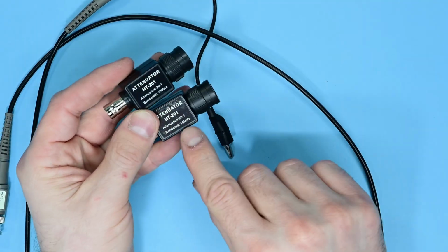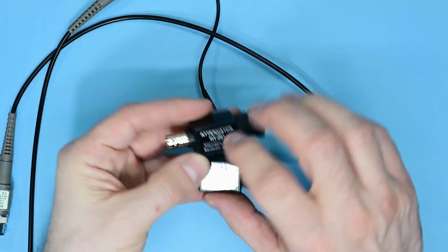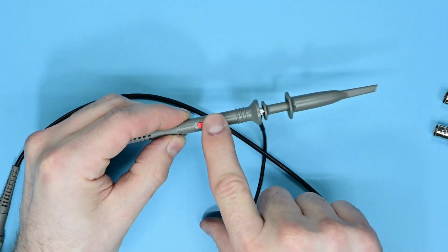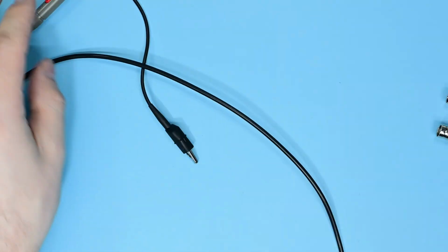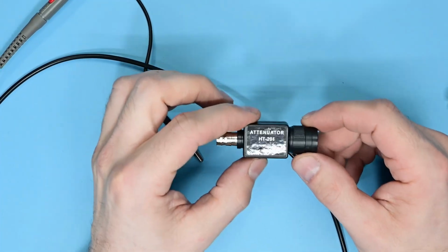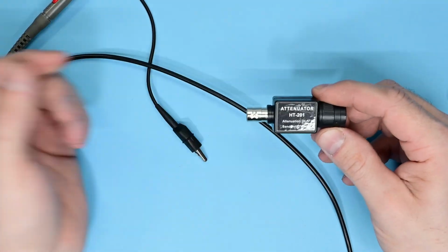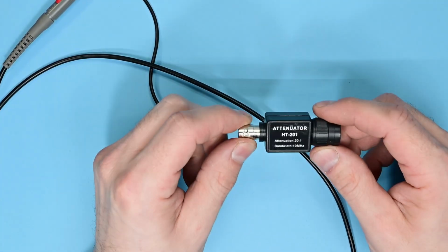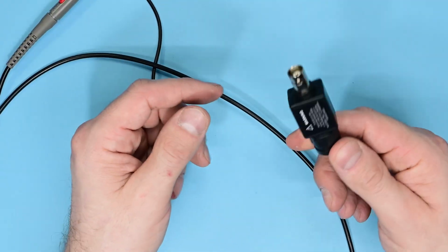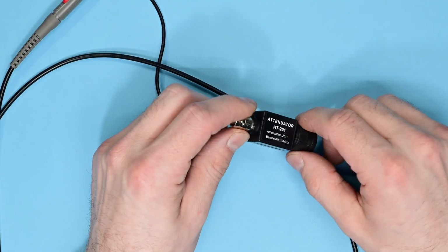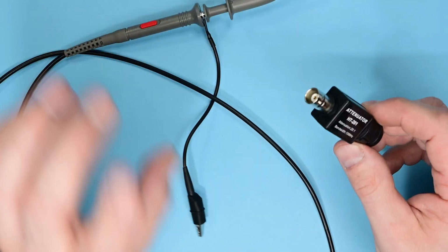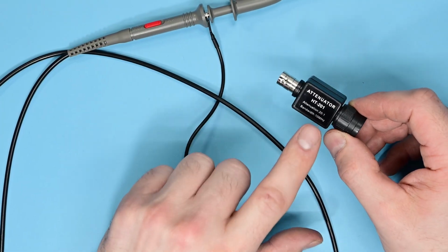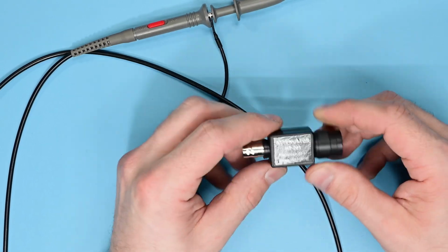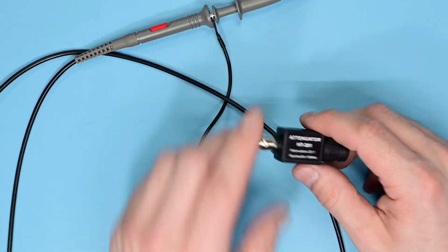So these are also attenuators. These ones, however, have a 20-to-1 ratio instead of the 10-to-1 ratio that's found in a lot of this style of probe. So what that means is if we had a 20-volt signal, it would go into the scope as a 1-volt signal. So again, this provides protection. Did you use protection? It provides a little bit more than what these ones do. However, keep in mind that does reduce the resolution or the resolving power of the scope, so the signal is going to be a little bit less clear.